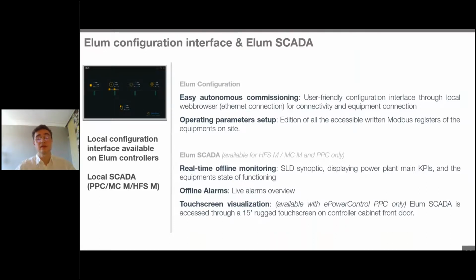This Elum configuration interface is available anytime, from commissioning to anytime during the operation and maintenance of the site, and you can access it just by connecting a computer physically to this ePower Control with an Ethernet wire. This way you will be able to proceed with the autonomous commissioning of your controller, being able to make connection tests during the first installation, configure the minimum genset loading at different set points, and make special arrangements with the local team. So you're really able to manage the control strategy of this ePower Control unit thanks to this interface.